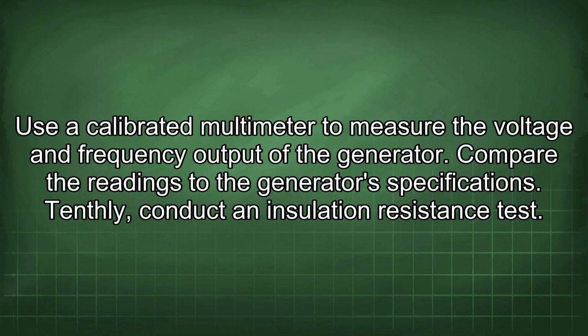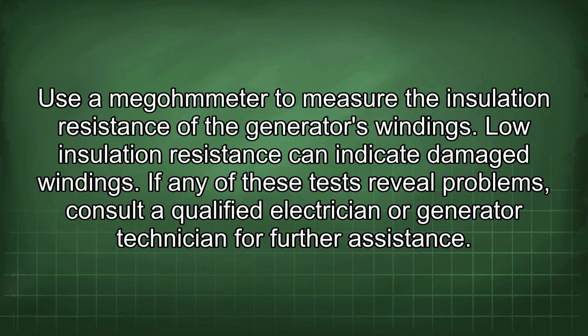Tenthly, conduct an insulation resistance test. Use a megohmmeter to measure the insulation resistance of the generator's windings. Low insulation resistance can indicate damaged windings. If any of these tests reveal problems, consult a qualified electrician or generator technician for further assistance.